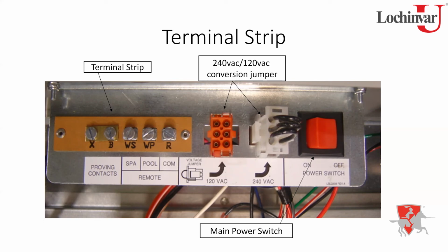One of the big reasons we put it in the 240 position is that if you had it in the 120 position and you wired 240 to it, you may smoke something. In 240, you're not going to if you put 120 to it. Yeah, you release what we call the magic smoke from the board, and that's a bad thing. And it doesn't go back in.